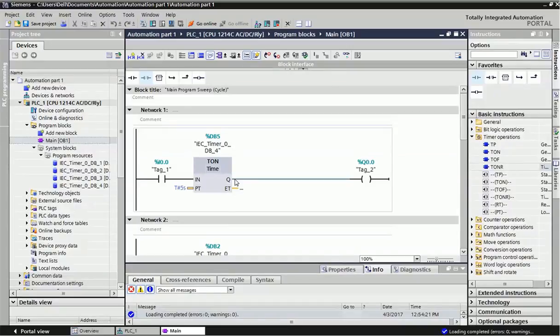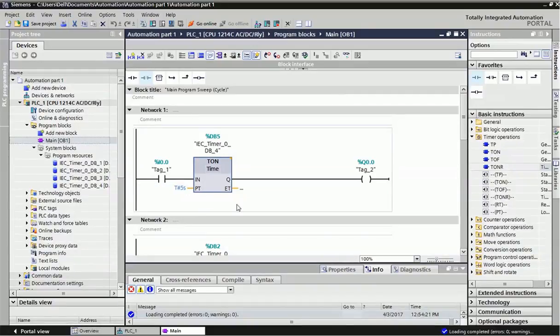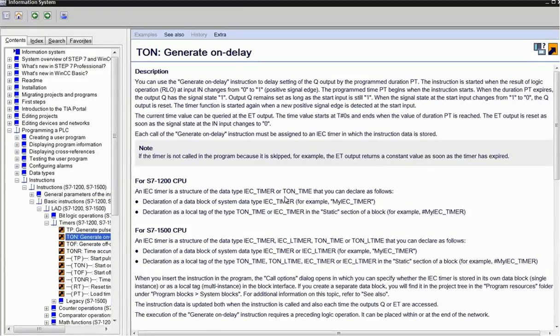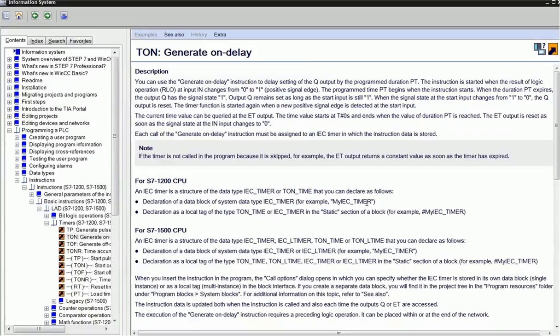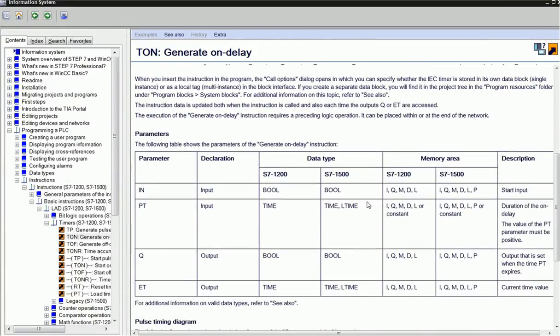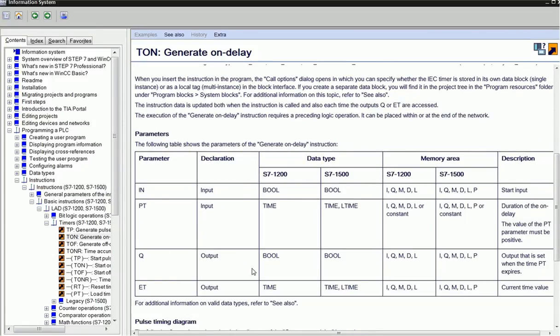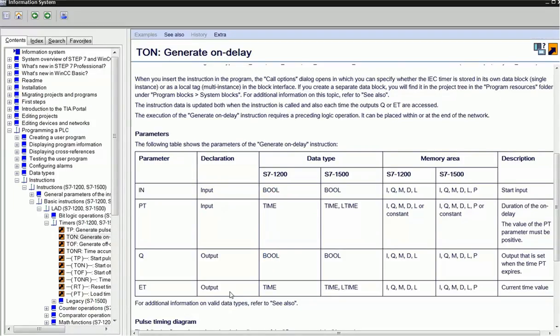I've taken the TON timer. TON timer has four types of parameters: input, output, preset time, and elapsed time. TON timer is generally used for giving on-delay. When you want to turn on an output after a preset time, we use the TON timer. Input and output are both Boolean data type, and preset time and elapsed time are both time data type. This time is stored in 32 bits.